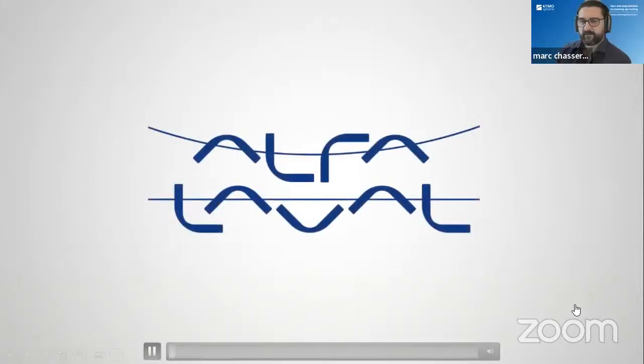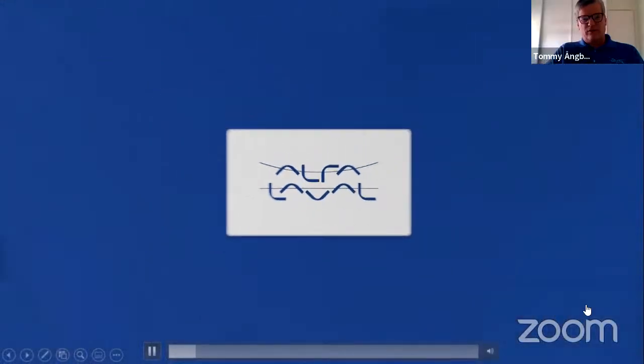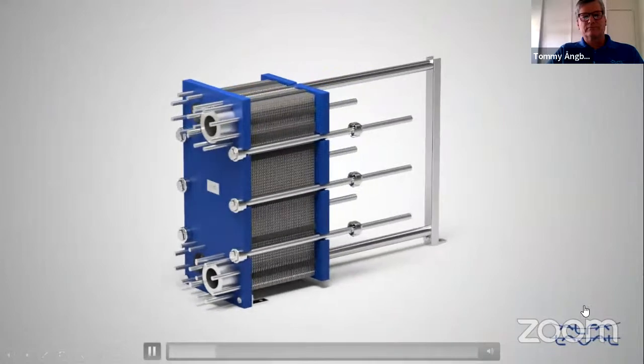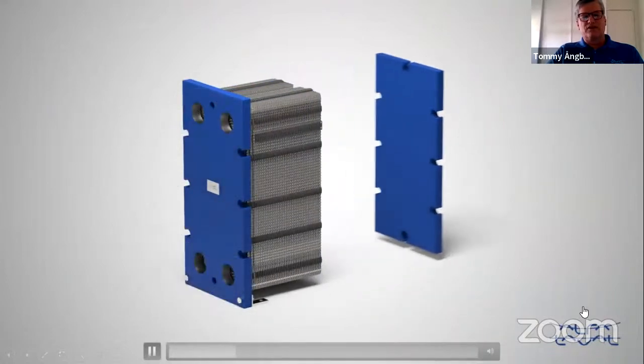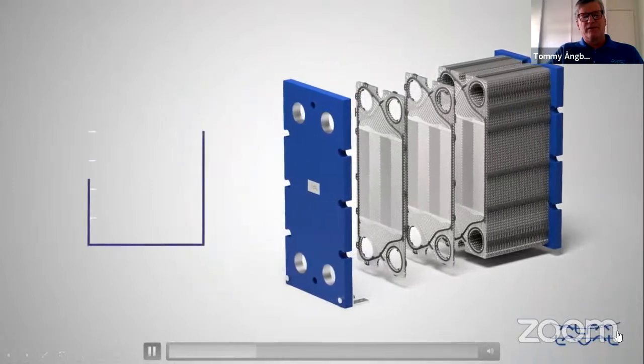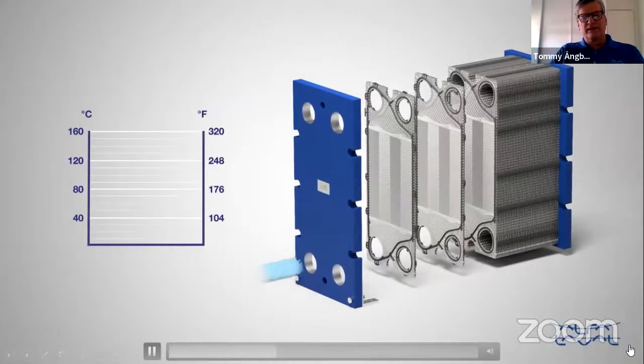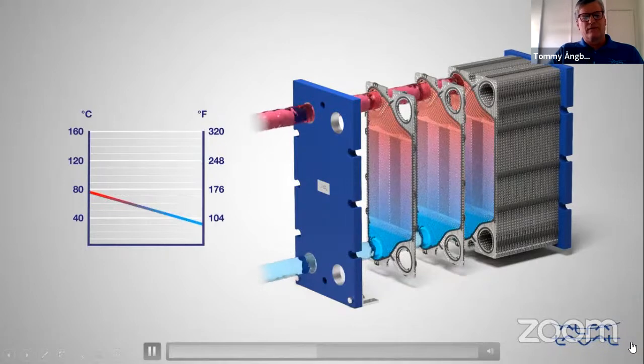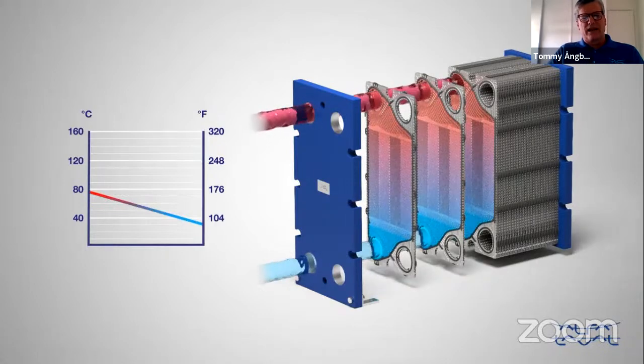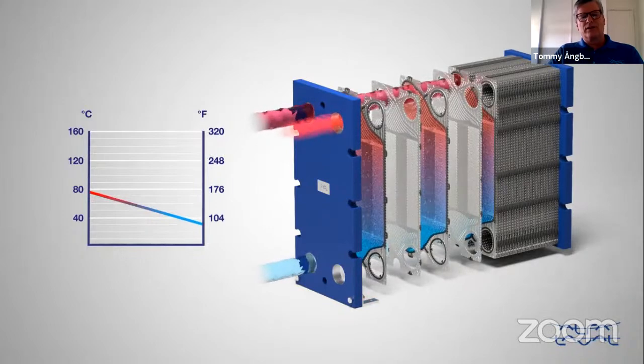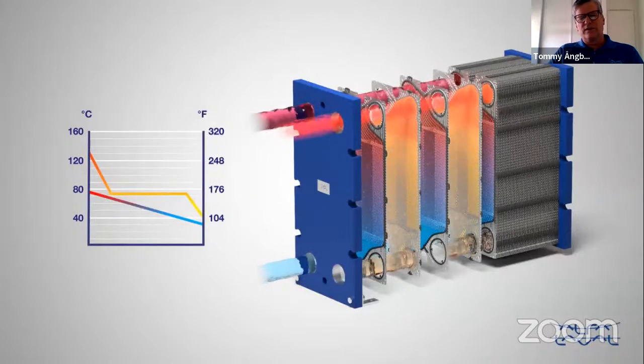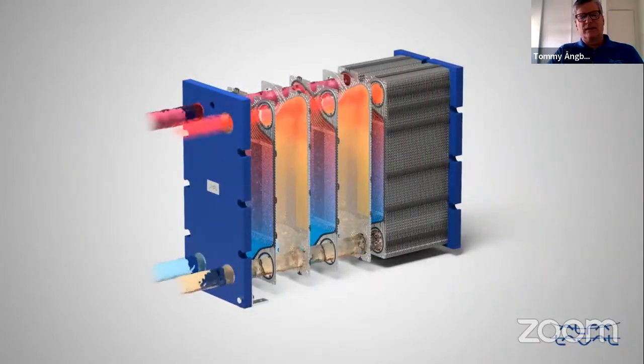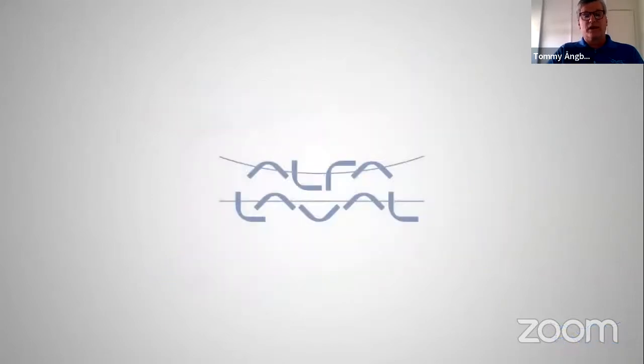But this is a little film that shows the subcooled condenser in a heat exchanger. We open the heat exchanger to look inside. We have the temperature profile to the right. Here we can see the cold water coming in, for example, being heated from 40 to 80 degrees. And on the other side, we will see how the hot ammonia gas from the compressor comes in, being desuperheated, condensing, and in the end it's liquid that is subcooled coming out of the heat exchanger. That's how we can do that in a very compact way, with a very small charge of ammonia as well.